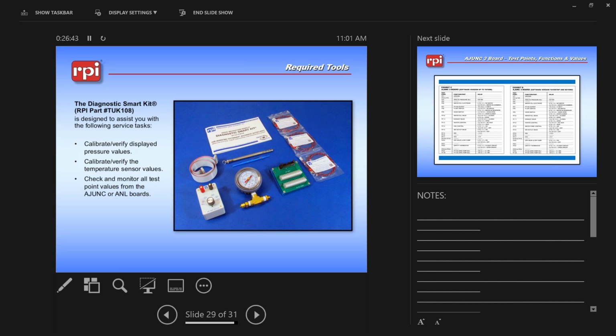To get started, all you're going to do is take the ribbon cable and connect it to your test point board, which is then going to get connected to the right-hand side of your AJUNC board. And then you're going to take whichever connector on the right-hand side is for your particular board. You're going to connect it to the test box. And then that is going to get connected in the place of your temp sensor on the back side of the electronics cabinet at JP11.